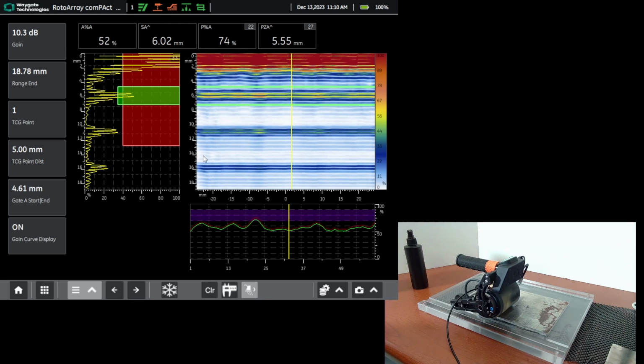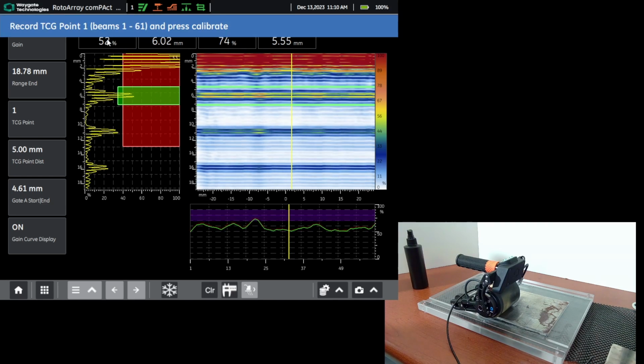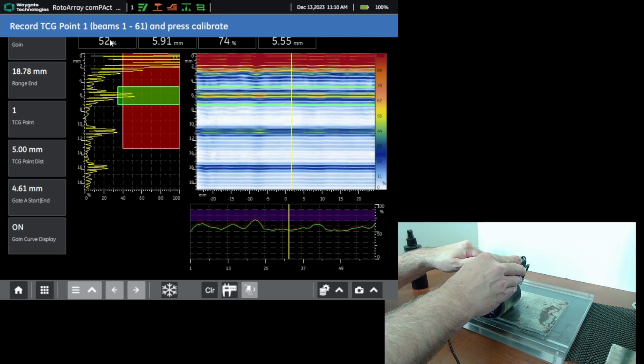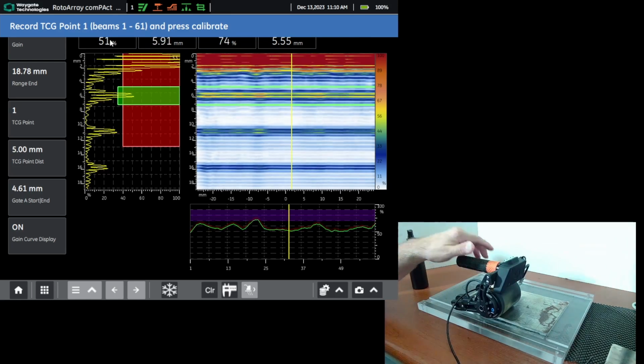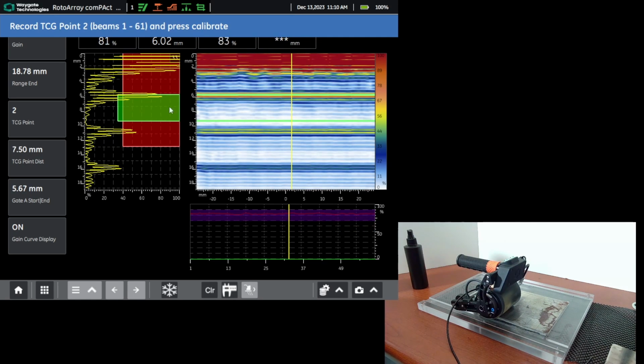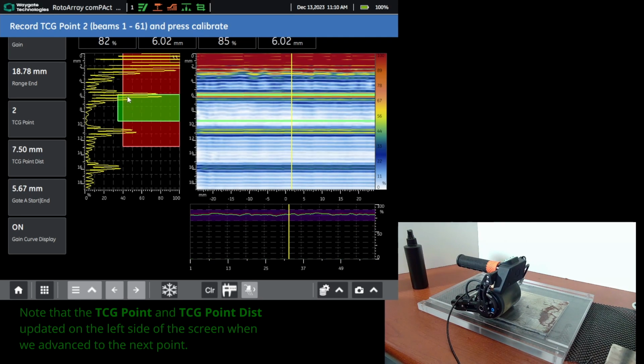Okay, we're ready to start our calibration. I hit the cal button once. It says I want to set up on my point 1. And I remember that's at 5 millimeters. I make sure I'm centered up on the step. I hit calibrate. And you notice the instrument adjusted the gains on the different beams to get an even amplitude the whole way across, and recorded that.